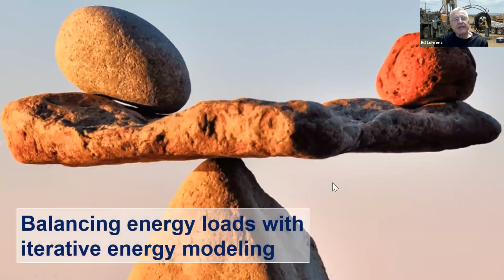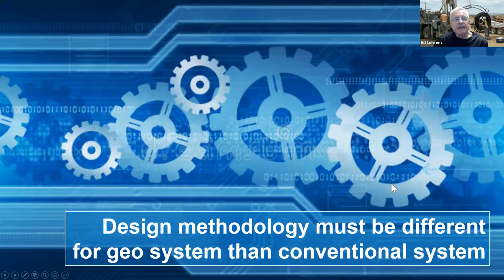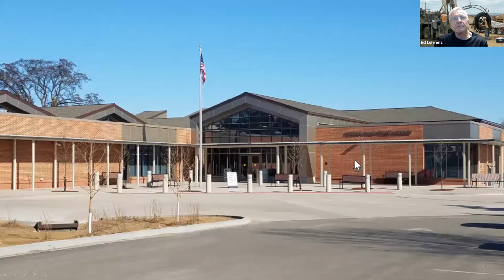So balancing the energy loads, one of the things that we've done with the design assistance program with Ottertail is to really work with the full design team, the architects, the mechanical designers, the building owners and the contractors that are building the systems, to try and, as much as we can, balance the amount of energy that building is going to reject to the ground versus how much it's going to take out. So the design methodology really has to be somewhat different than it would be for a conventional HVAC system.